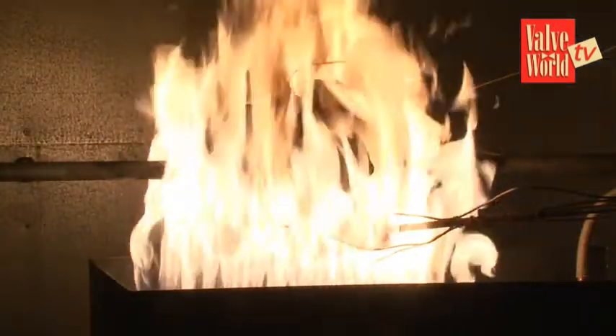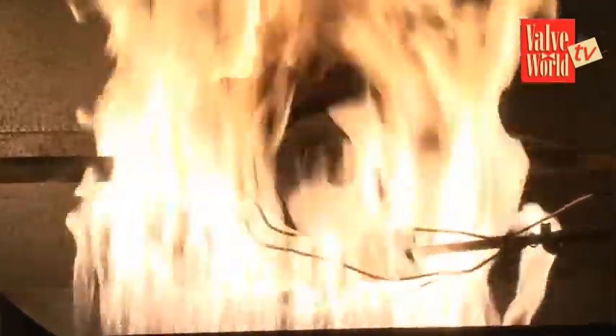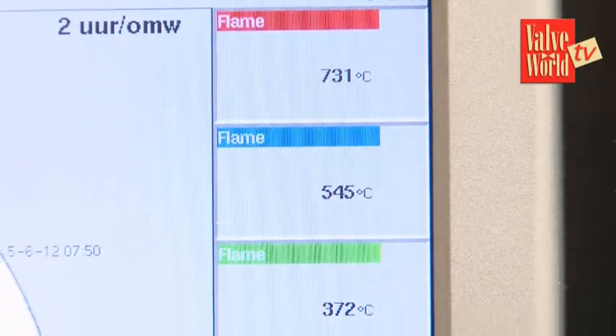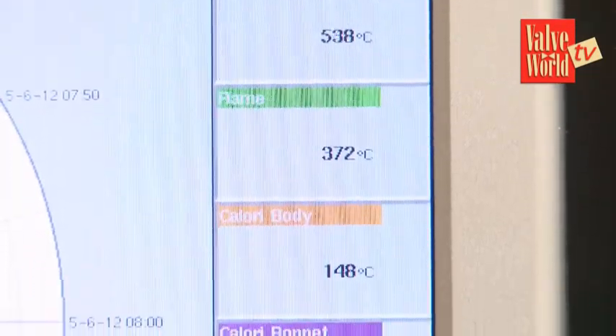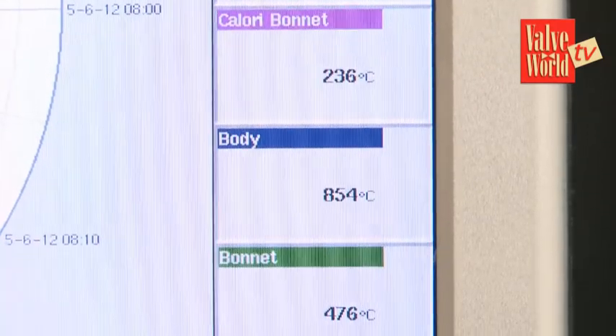So you're simulating a refinery fire — how do you know the temperature inside is hot enough? The temperatures are described in the procedure as well, so we monitor them with our recorder. During the fire, we have to confirm that all temperatures reach the required level within the time specified in the procedure.